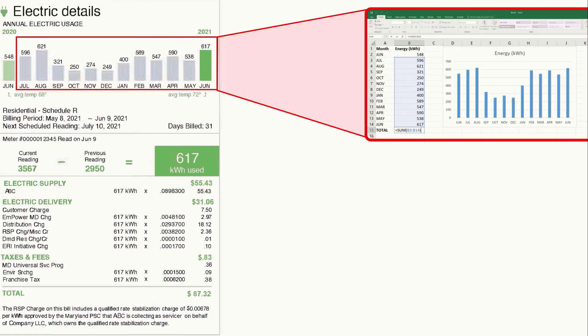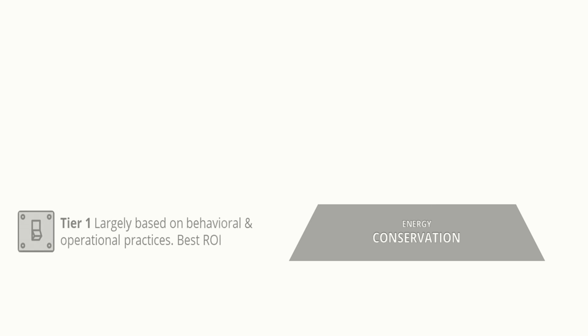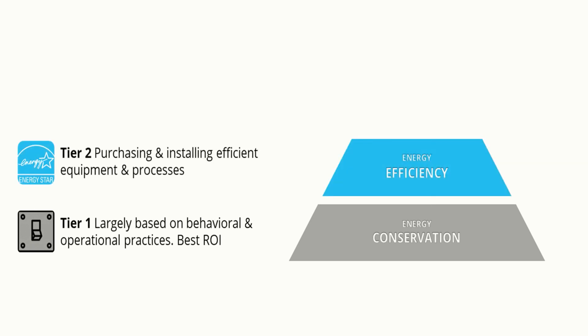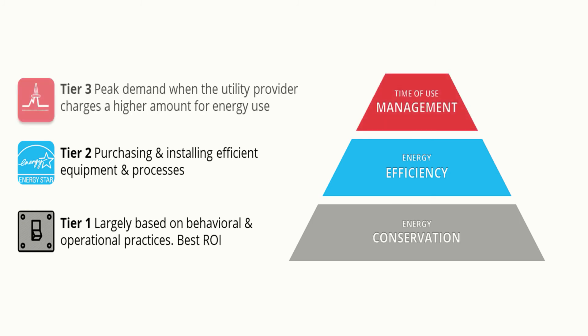We can add up each month over the course of the year to determine annual energy use. Entering the monthly energy values into a spreadsheet, I can easily calculate the annual energy use as 5,592 kilowatt hours. So to supply all of this energy, our solar electric system would need to produce 5,592 kilowatt hours. While we considered annual energy use in this example, daily or monthly values could be important when considering short-term use or working off-grid with batteries, helping meet maximum daily or monthly energy demands.